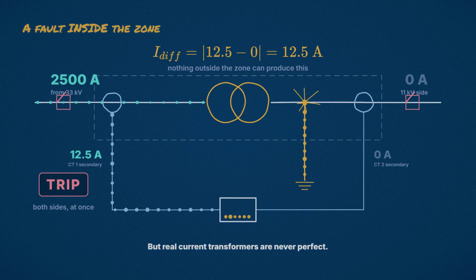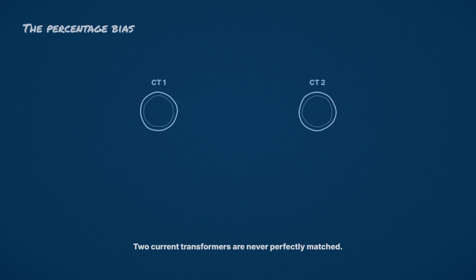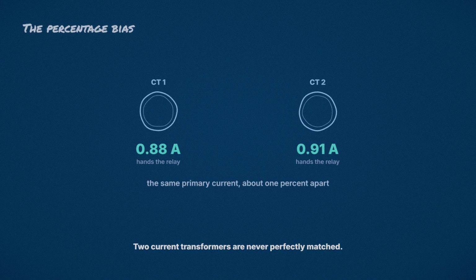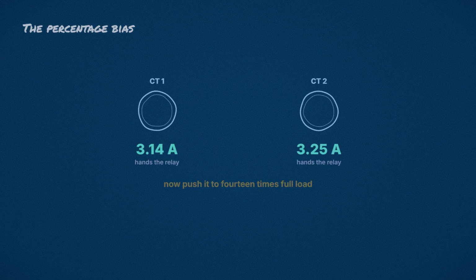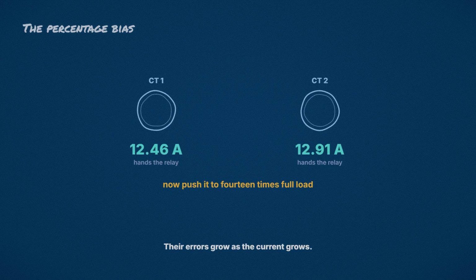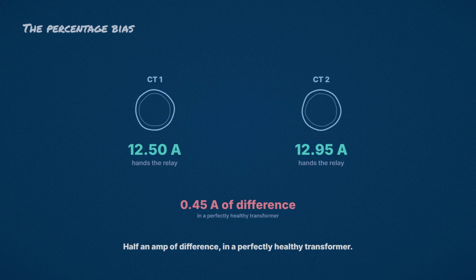But real current transformers are not perfect, and that is a problem. Two current transformers are never perfectly matched. Their small errors grow as the current grows. During that external fault, at 14 times full load, a 1% mismatch becomes nearly half an amp of differential current in a perfectly healthy transformer.